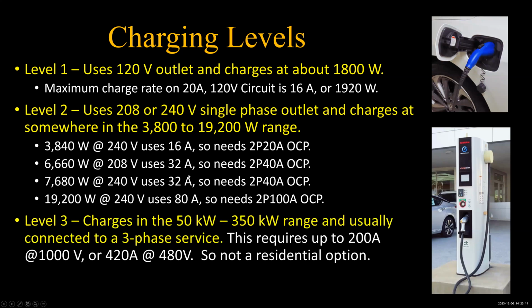Level 3, that's the fast charger. They're in somewhere in the 50,000 to 350,000 watt range, and generally connected to a 3-phase service. What that means is you're looking at, say, 200 amps at 1,000 volts DC, because level 3 charging is always DC as opposed to AC. Level 1 and level 2 are AC charging. So 200 amps at 1,000 volts or 420 amps at 480 volts. So that's not a residential option.